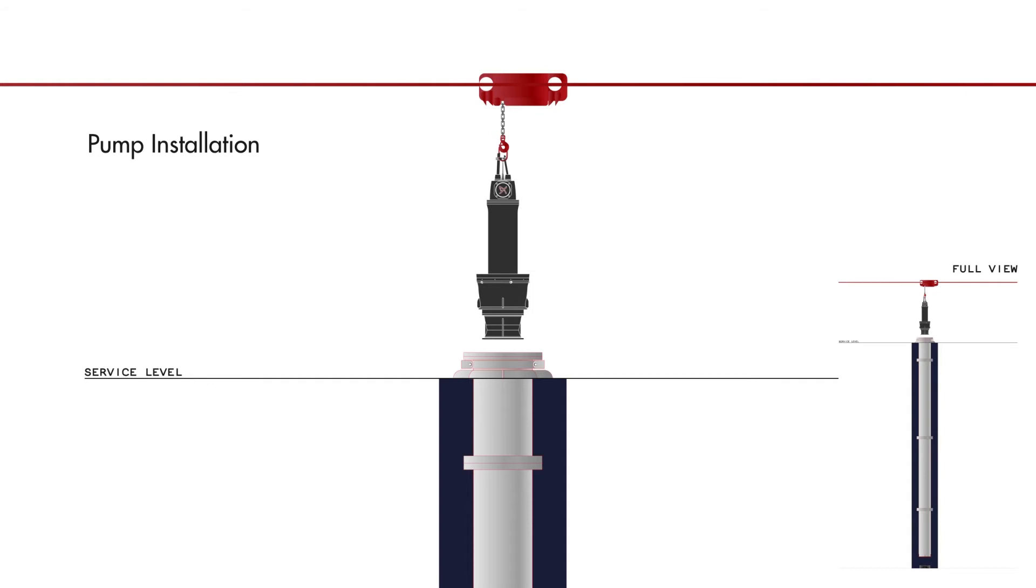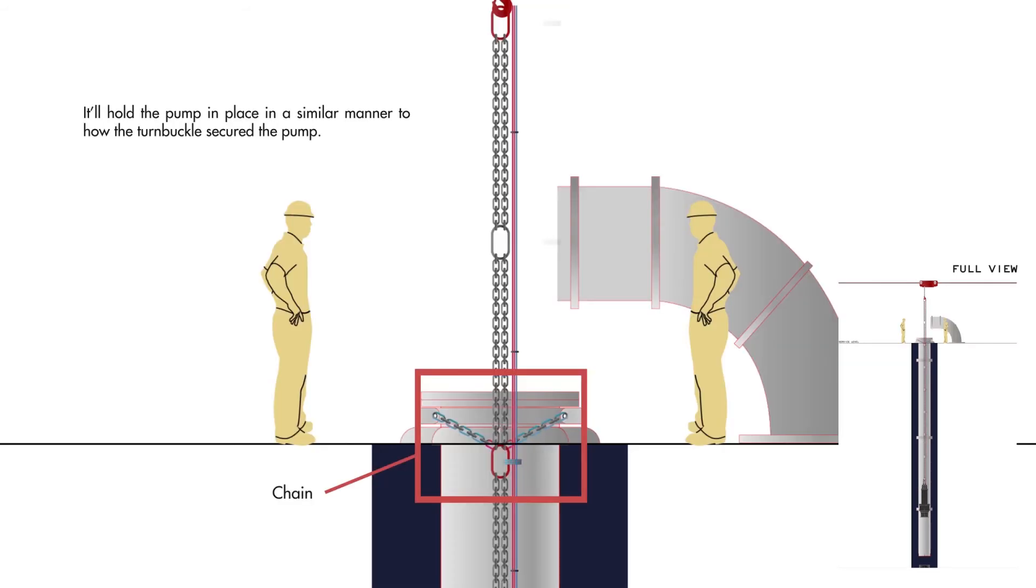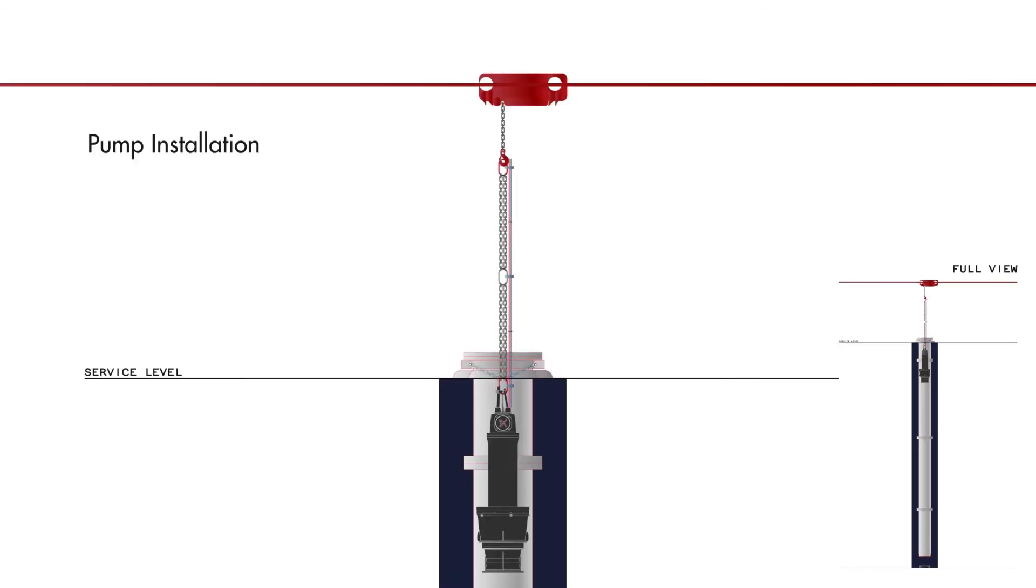When lowering down the pump, it often requires master links in the lifting equipment. In those cases, it is necessary to use two short support chains to hold the pump in place while changing position from one master link to another with the lifting hook.